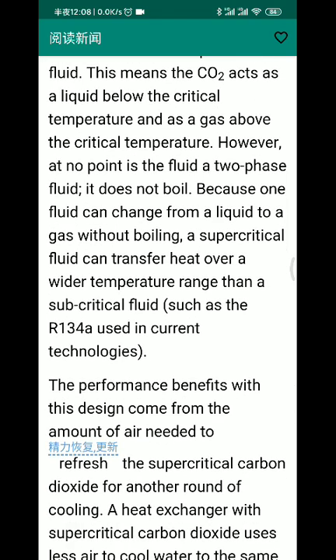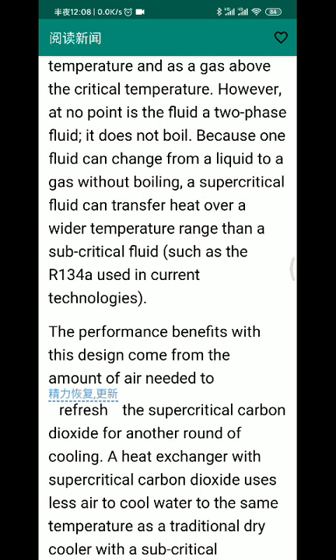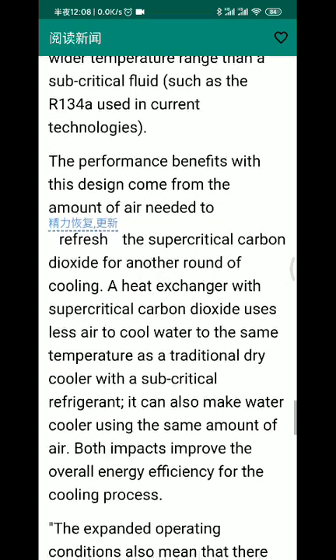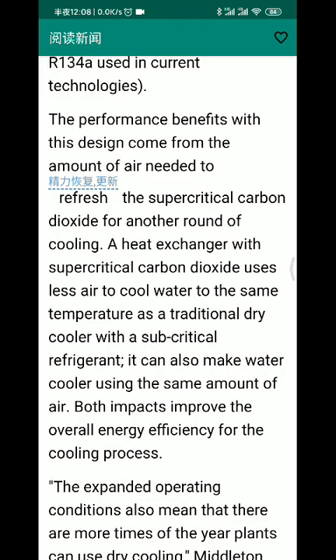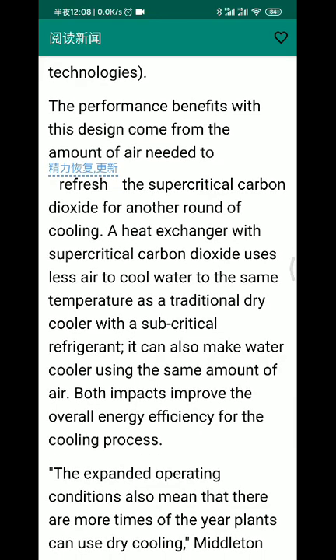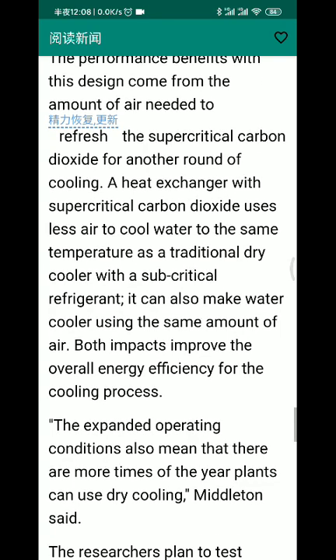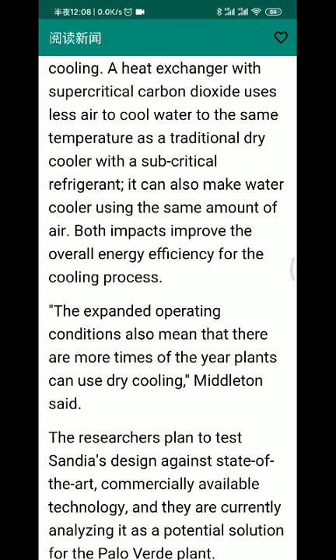The performance benefits with this design come from the amount of air needed to refresh the supercritical carbon dioxide for another round of cooling. A heat exchanger with supercritical carbon dioxide uses less air to cool water to the same temperature as a traditional dry cooler with a subcritical refrigerant. It can also make water cooler using the same amount of air. Both impacts improve the overall energy efficiency for the cooling process.